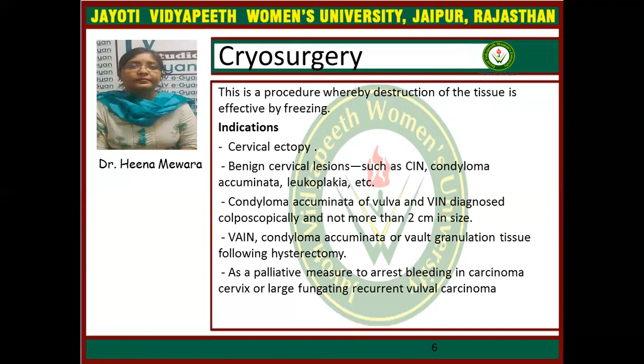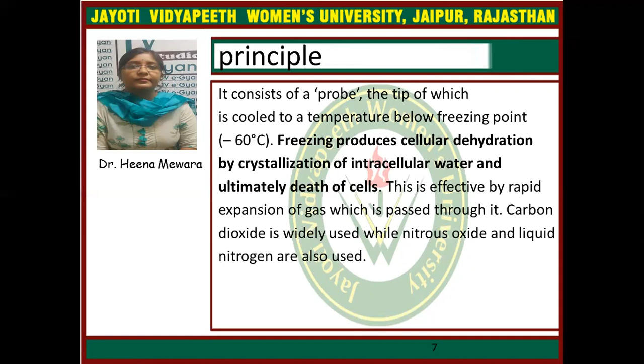Cryosurgery consists of a probe, the tip of which is cooled to a temperature below the freezing point, that is less than minus 60 degrees centigrade. Freezing produces cellular dehydration by crystallization of intracellular water and ultimately death of the cell. This is effected by rapid expansion of gas which is passed through it. Carbon dioxide is widely used, while nitrous oxide and liquid nitrogen are also used for this procedure.